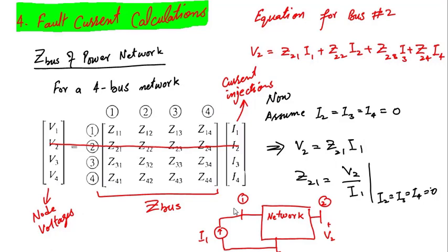Okay, so what will be its impact on the voltage V1 of bus 1? That is described by the diagonal entry. And what is its impact on voltages of other nodes, node 2, 3 and onward? That is described by the off diagonal entries. So it is known as the transfer effect. Injection at one node, how much voltage it will produce on the other node. This is known as the transfer effect. So that is described with the help of these transfer impedances. Further, we will see in a later slide how to use these transfer impedances for the calculation of the current contributions.